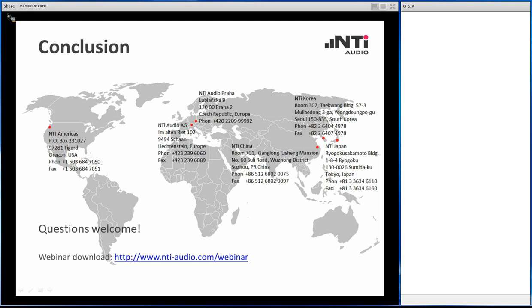A second question regarding the reference microphone, whether the system would also support reference microphones from other manufacturers. The answer is yes. If you already have a high precision class 1 microphone, then you can of course use that and connect it to the system for your application. The FX100 has a built-in phantom power supply and ICP power supply, so it should be possible to directly connect the microphone to the instrument without the need of an external power supply.